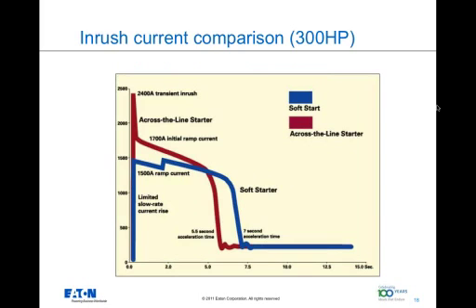In a typical system, the motor during the initial phase draws about 6 to 8 times FLA for inrush current when an across-the-line starter is used. That same requirement for inrush current drops down to 3 to 4 times FLA when a soft starter is used. Again, that is a reduction of about 40 to 50% of inrush current.